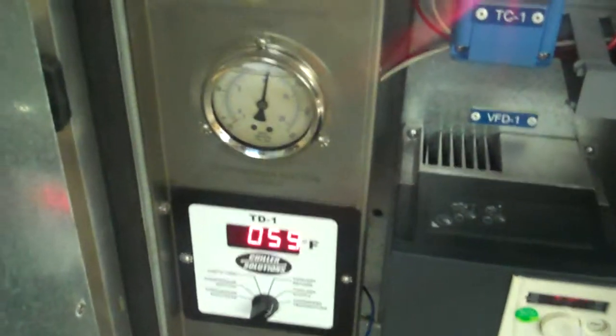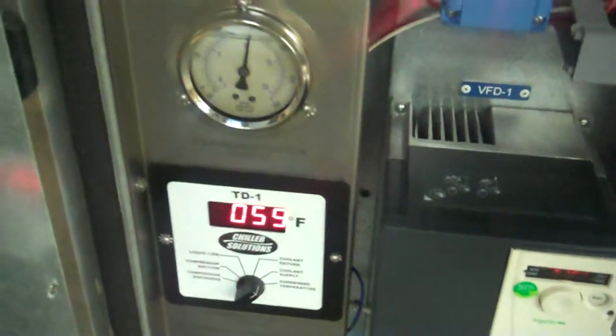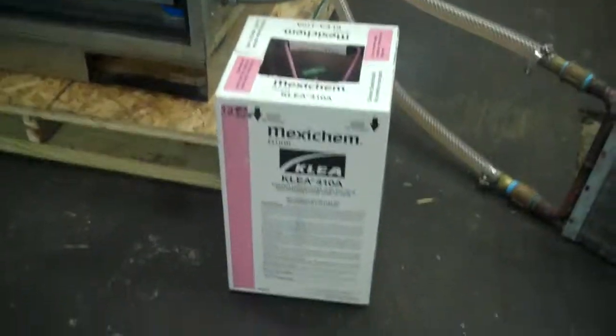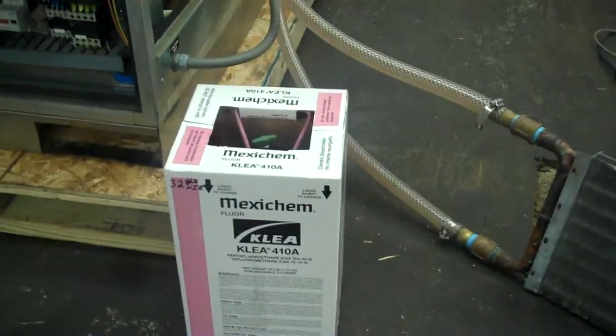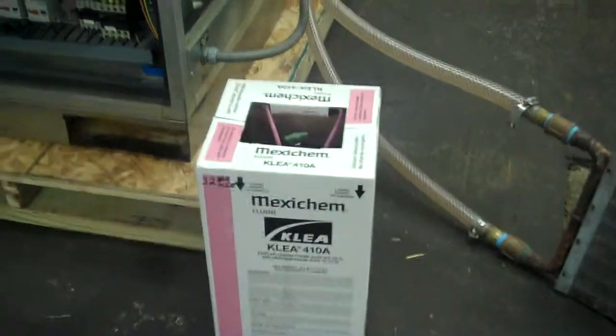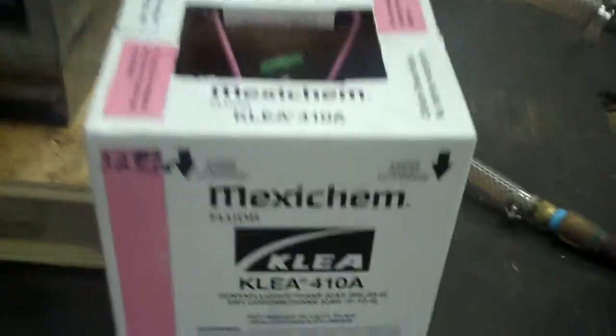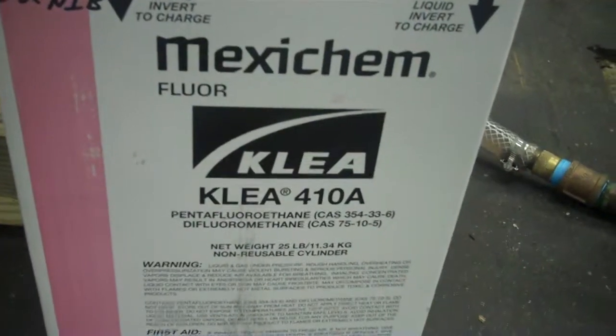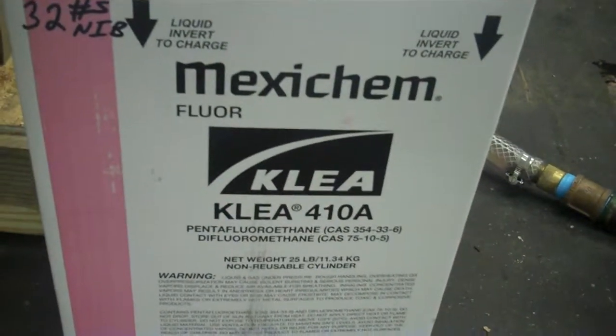Again, we just set up a loop right here, which comes to this coil that we have to give us some type of load. See, we're down to about 59 degrees Fahrenheit right now. As mentioned to the customers buying this particular unit, which is intended for a brewery application, we did find a cap inside that was loose, and it leaked out a little bit of the refrigerant. So another nice thing is this uses R410A refrigerant. It does run at higher pressures as compared to R22.